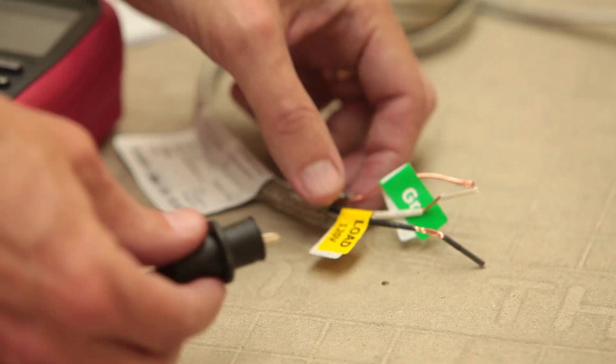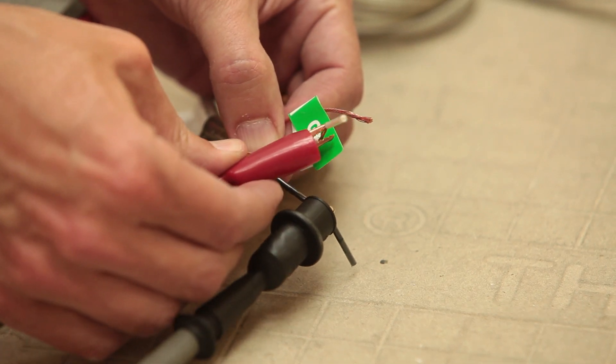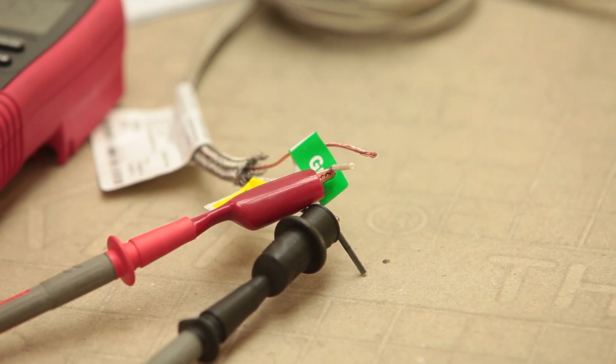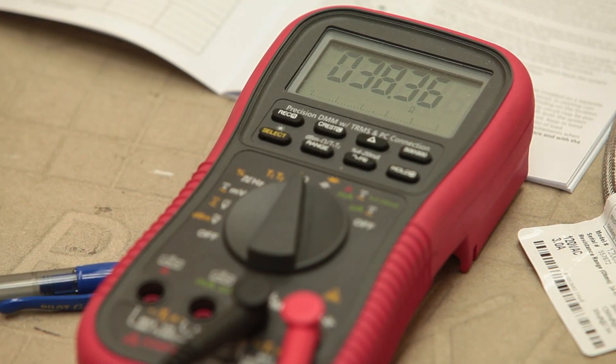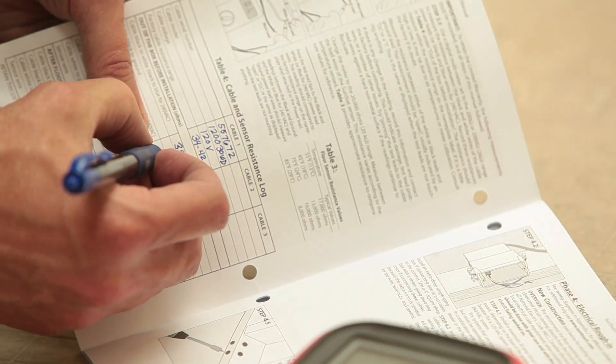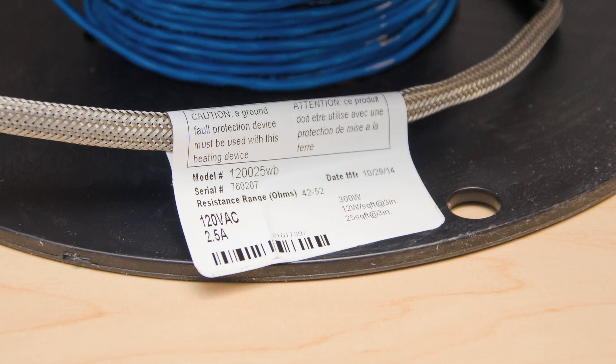Set the electrical meter to the 200 ohm range and measure the readings between the black and white wires. This will be black and blue for the 240 volt WarmWire. Record the ohm reading in the out-of-box before installation table in the installation manual. The number should be within the range printed on the nameplate label.